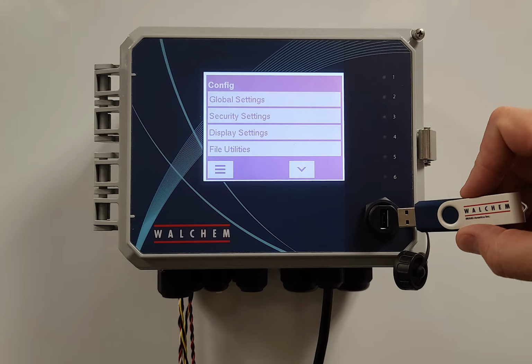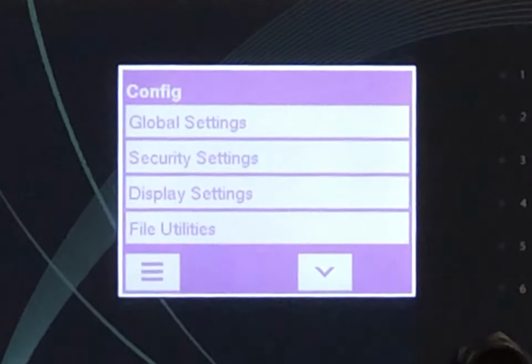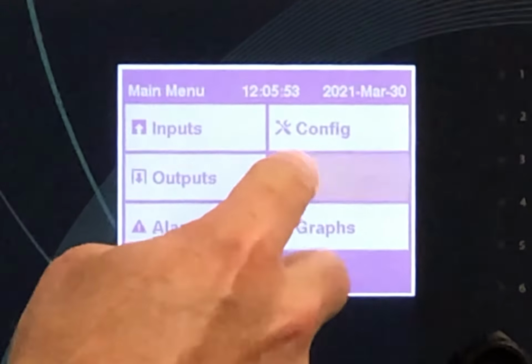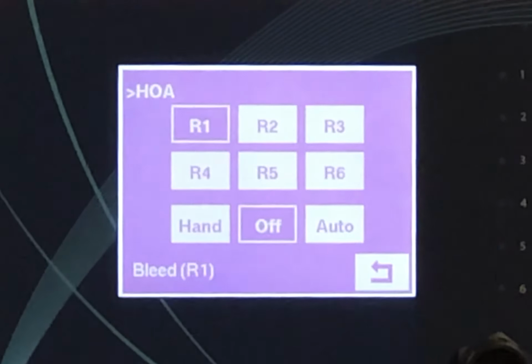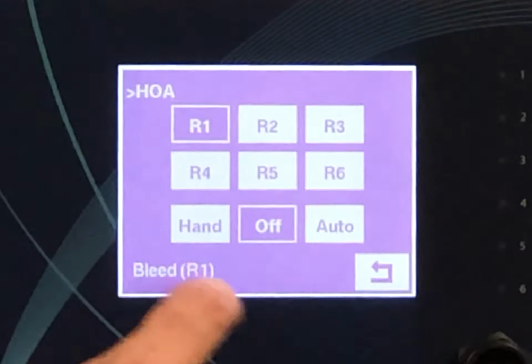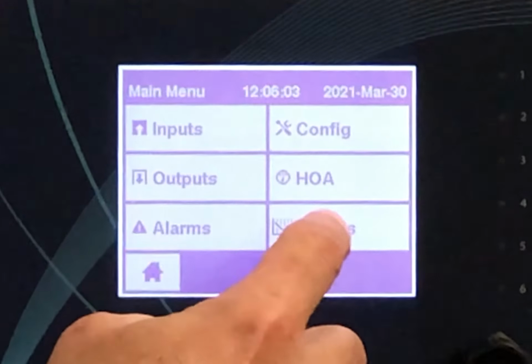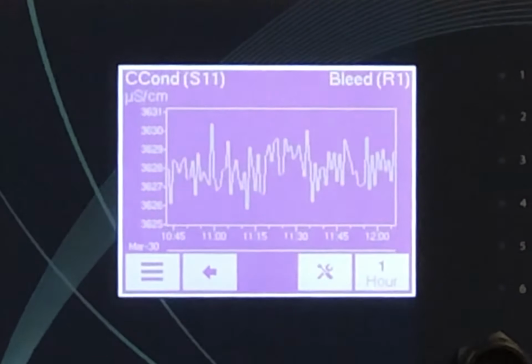Config allows the user to get any files locally from the USB drive on the front of the controller, set up the email report page, and set up the security level on the controller. HOA. This page allows the user to manually turn the relays on and off. And graphs. This option allows the user to set up graphs which can be visually seen on the controller screen. The graphs can show sensor values, analog inputs, analog outputs, and relays.